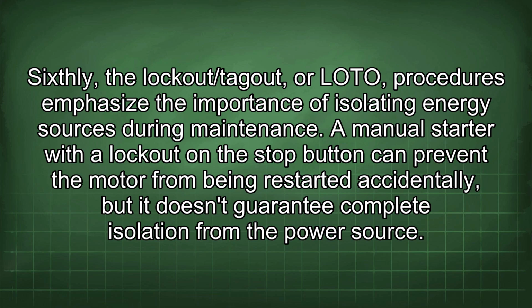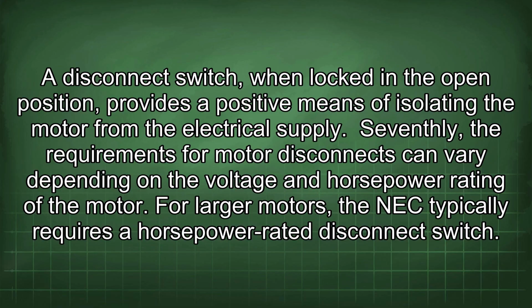Sixthly, the lockout/tagout, or LOTO, procedures emphasize the importance of isolating energy sources during maintenance. A manual starter with a lockout on the stop button can prevent the motor from being restarted accidentally, but it doesn't guarantee complete isolation from the power source. A disconnect switch, when locked in the open position, provides a positive means of isolating the motor from the electrical supply.